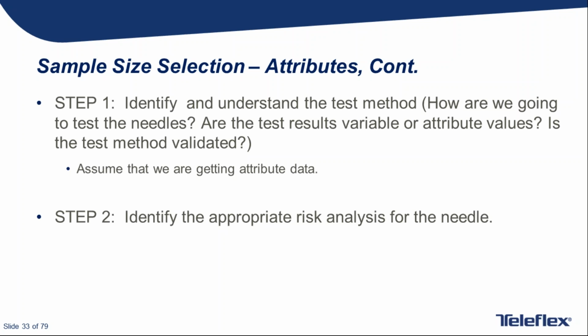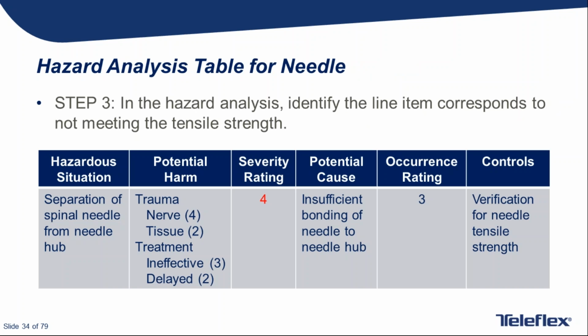Starting with risk, though, we're going to identify the appropriate risk analysis for the needle. And then engineering knowledge tells us that tensile strength is related to the failure mode or hazardous situation of separation from the needle hub. So we go to the risk analysis, we determine that a severity rating of 4 applies to this particular defect. One way to do a hazard analysis is to list all the potential harms, as is done here, and then, to be most conservative, choose the one with the highest severity rating and test to that level. The occurrence rating does not come into the selection of sample size in this case.